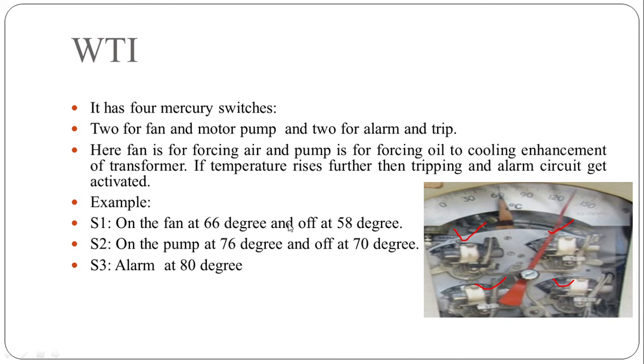Now after that if temperature further rises and it rises up to 100 degree, switch 4 is set to operate at 100 degree. So when temperature reaches 100 degree switch S4 operates and it initiates the tripping circuit of the transformer. In case of tripping the transformer gets completely isolated from supply. So these are the functions of 4 switches in case of winding temperature indicator.